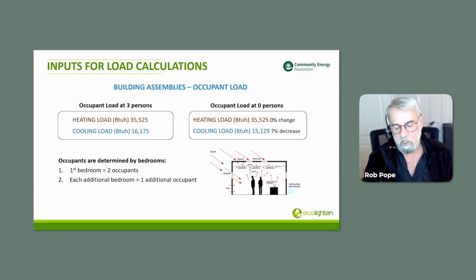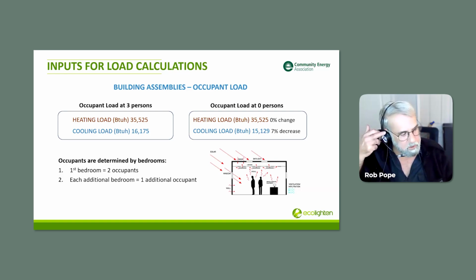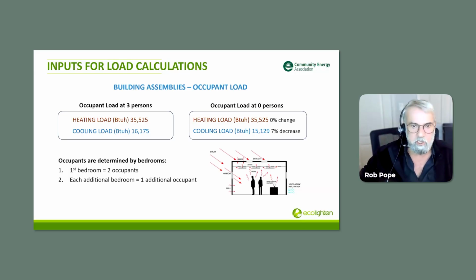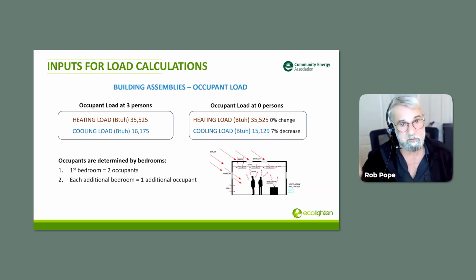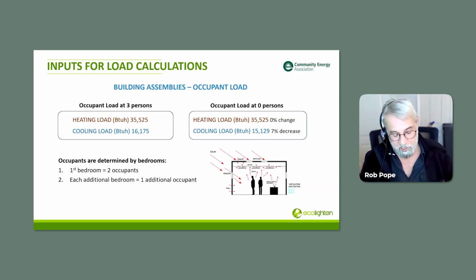Opportunities for customization, if it's apparent there's going to be major peak load conditions. I want to entertain in the winter, I'll entertain in the summer, I've got a pool out there, we've got lots of kids and grandkids, and there'll be 20 of us in the house cooking dinners and all that kind of stuff. Doors will be open, people running in and out, kids wet, bathing suits on and towels. That is a prime peak load condition. You've got 2 choices: you can expect it to be uncomfortably warm and humid in the house in that condition, or we can design the system to accommodate that intermittently when those occasions are occurring.